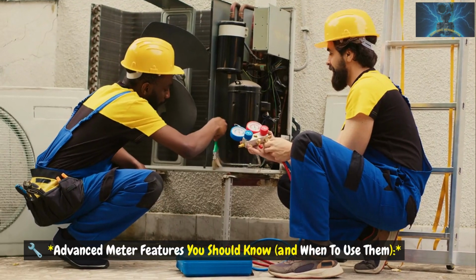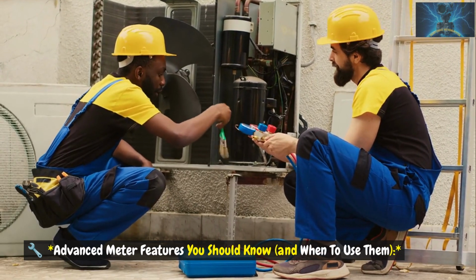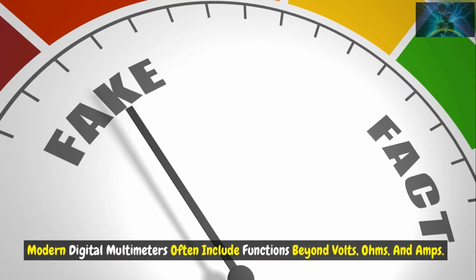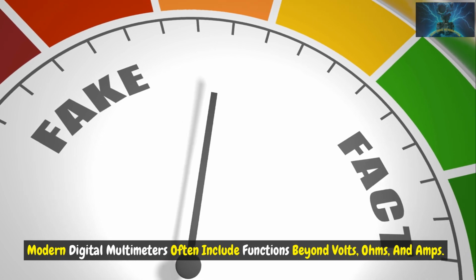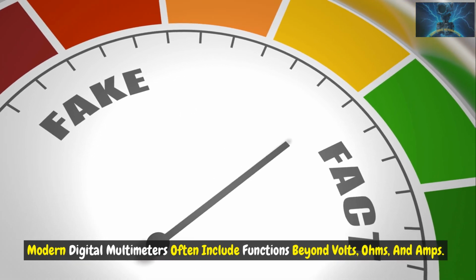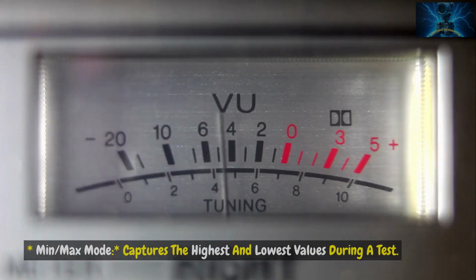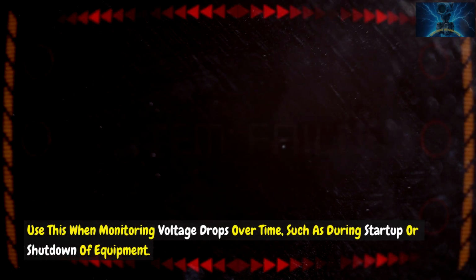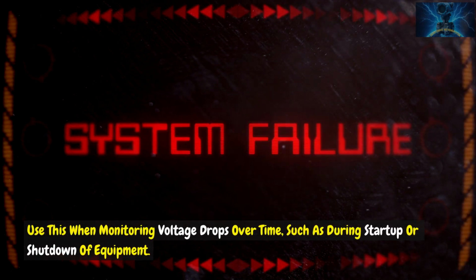Advanced meter features you should know and when to use them. Modern digital multimeters often include functions beyond volts, ohms, and amps. Here are a few to master. Min Max Mode captures the highest and lowest values during a test. Use this when monitoring voltage drops over time, such as during startup or shutdown of equipment.